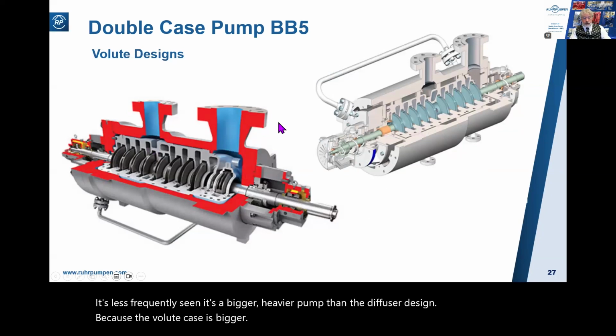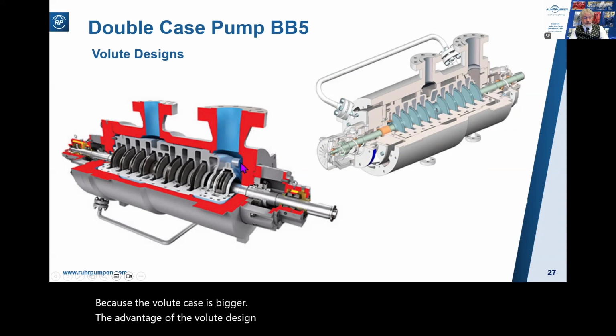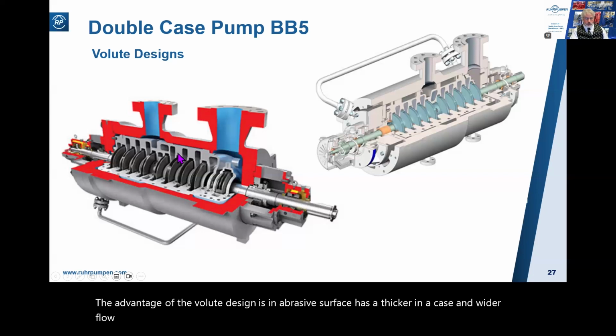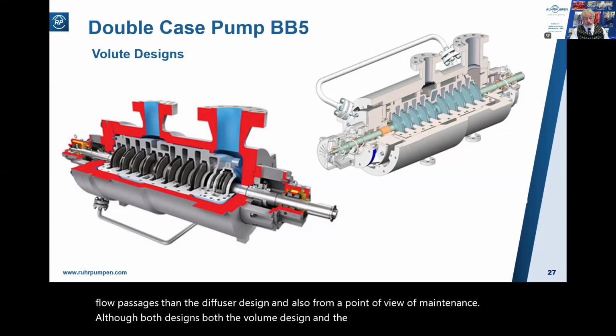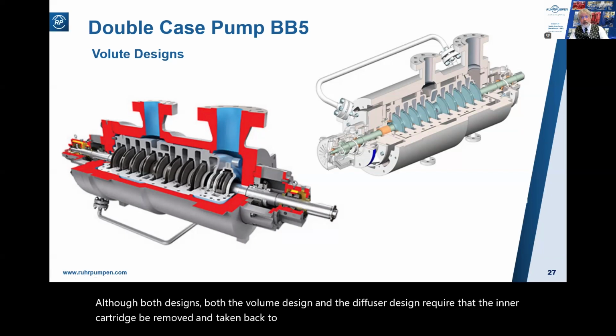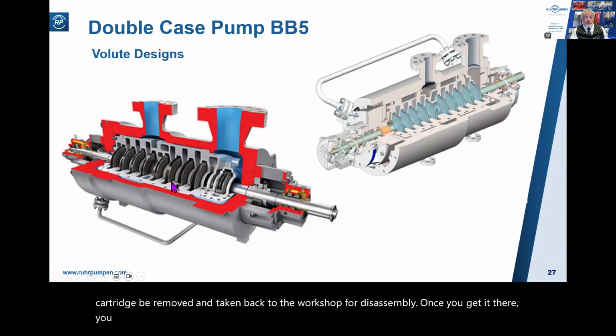The advantage of the volute design is in abrasive service: it has a thicker inner case and wider flow passages than the diffuser design. And also from a point of view of maintenance, although both the volute design and the diffuser design require that the inner cartridge be removed and taken back to the workshop for disassembly, once you get it there, you can remove the upper case half of a volute design and remove the rotor as a complete assembly.